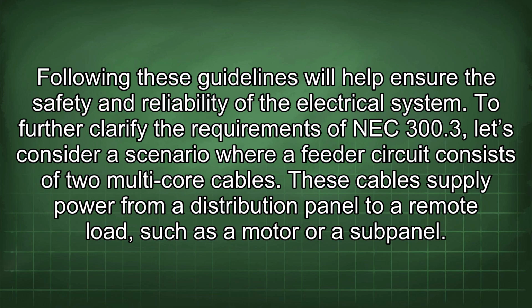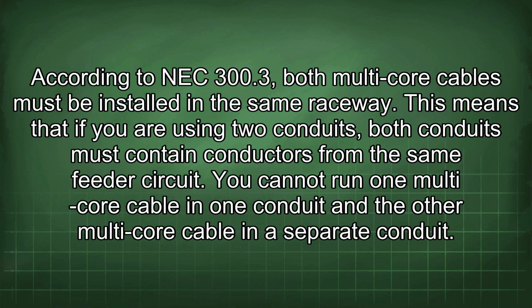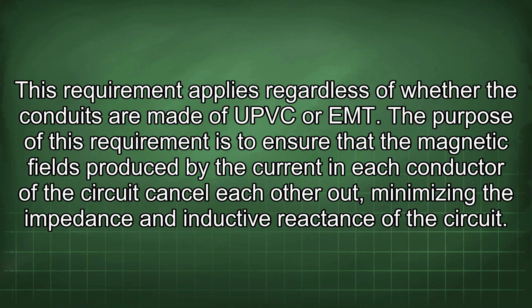To further clarify the requirements of NEC 300.3, let's consider a scenario where a feeder circuit consists of two multi-core cables. These cables supply power from a distribution panel to a remote load, such as a motor or a sub-panel. According to NEC 300.3, both multi-core cables must be installed in the same raceway. This means that if you are using two conduits, both conduits must contain conductors from the same feeder circuit. You cannot run one multi-core cable in one conduit and the other multi-core cable in a separate conduit. This requirement applies regardless of whether the conduits are made of PVC or ENT.